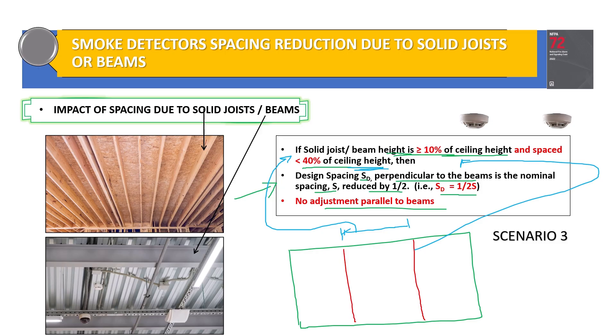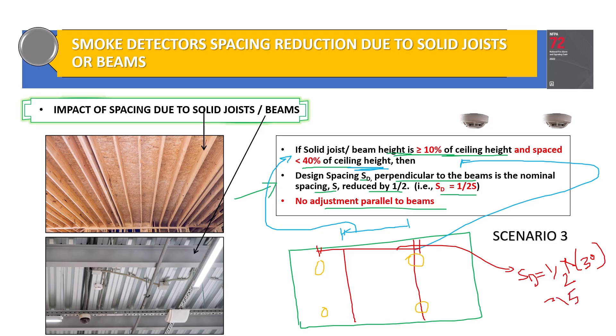I will explain Scenario 3 with an example. The distance between smoke detectors perpendicular to the beam equals half S — since S is 30 feet as per NFPA 72, SD equals 15 feet in that direction. Parallel to the beam or joist, SD equals S, which is 30 feet. This is how we distribute the smoke detectors across the entire floor or building.